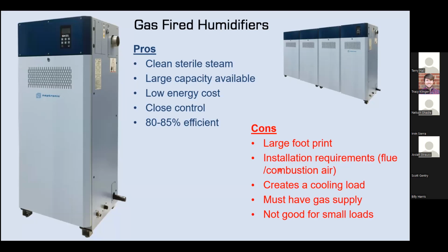And the huge benefit also to having multiple modules is redundancy. Remember I talked about the skin laboratory that was making the skin? Well, they had an air change every minute. You always need to have humidifiers running. And if one module goes into a drain cycle to refresh its water supply, you want to make sure that you have the rest of your modules running.